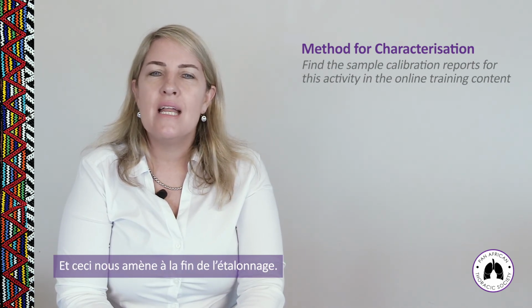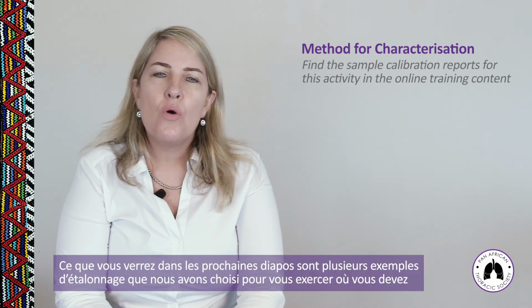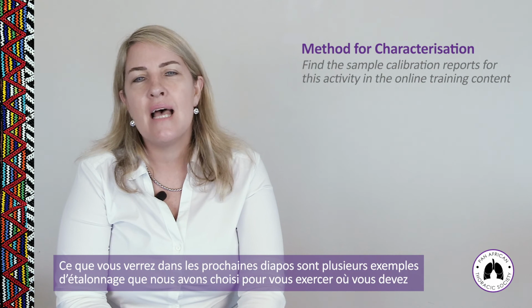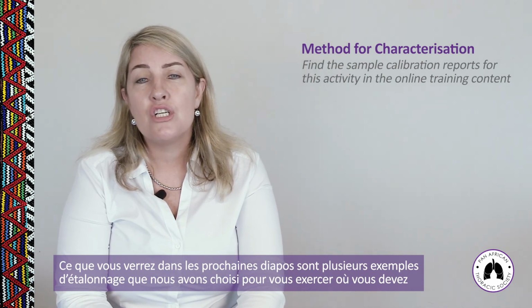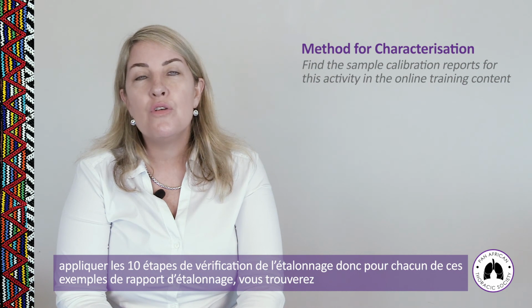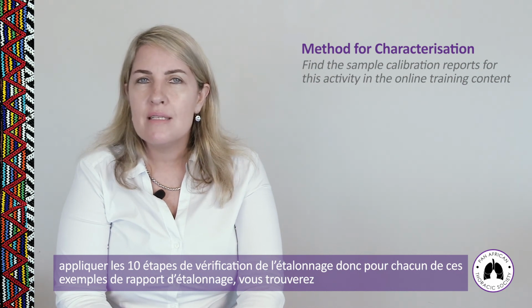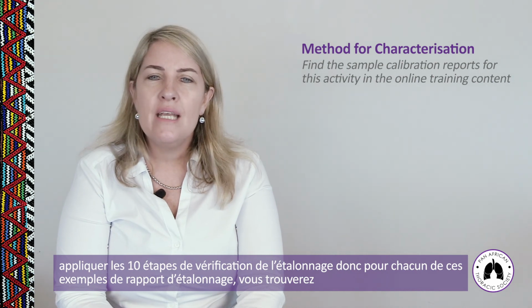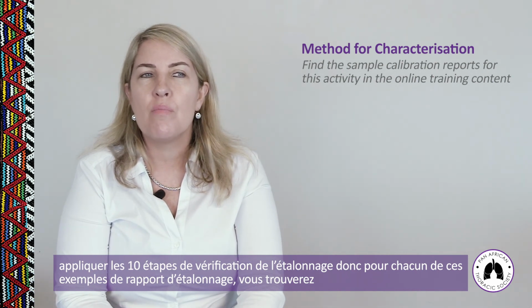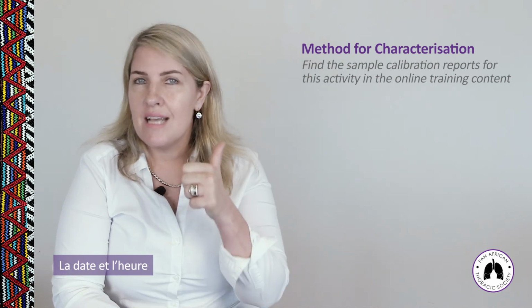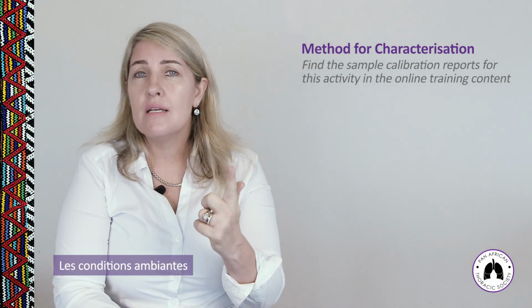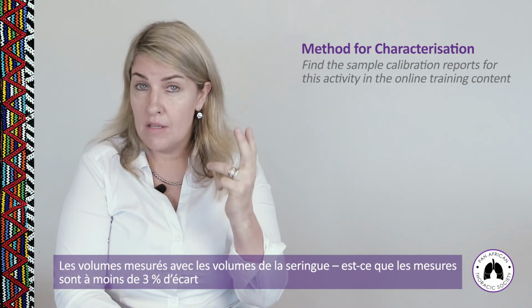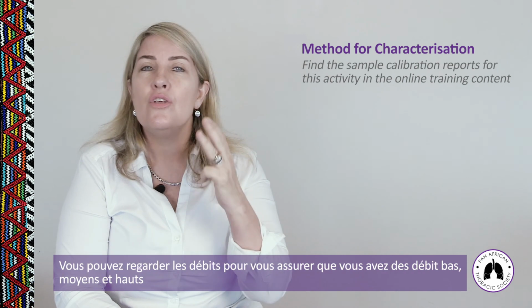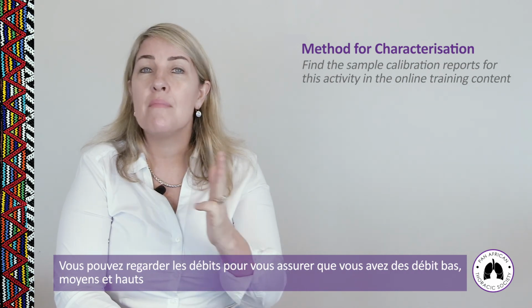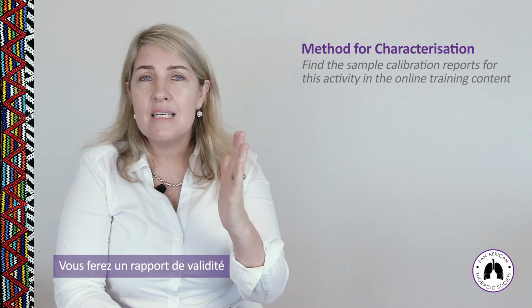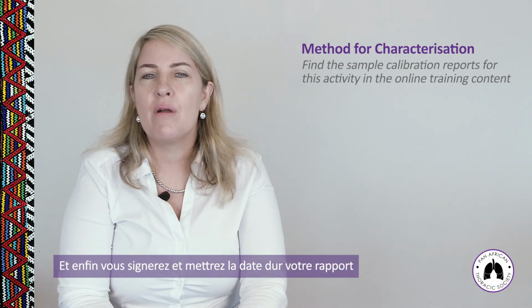And that brings us to the end of calibration. So what you will see in the slides to come is that there are various calibration examples that we have used for you to work on, where you apply your 10 steps to checking your calibration. So on each and every one of these example calibration reports, you could look to find the date and time, the ambient conditions, the measured volumes with the syringe volume. Is it within 3%? You could look at your flow rates to see that you've got low, medium, and high flow rates, make a validity statement, and then sign and date your calibration report.